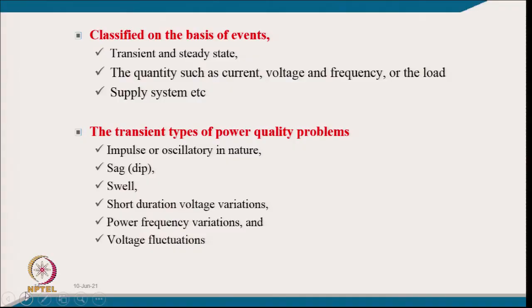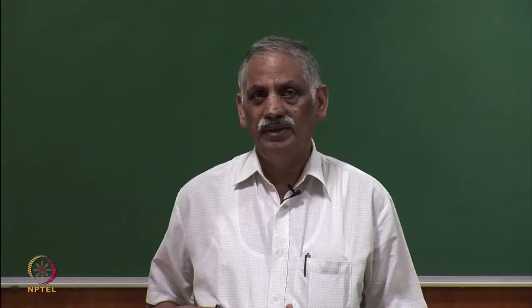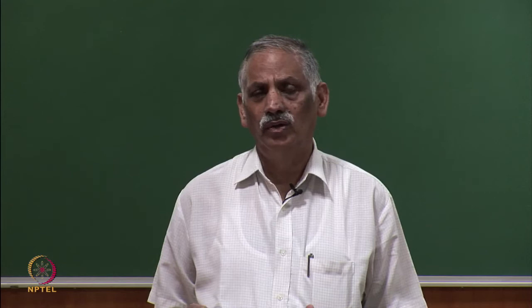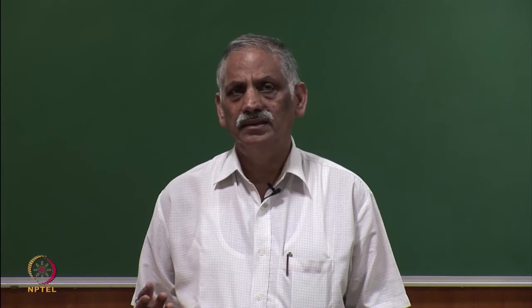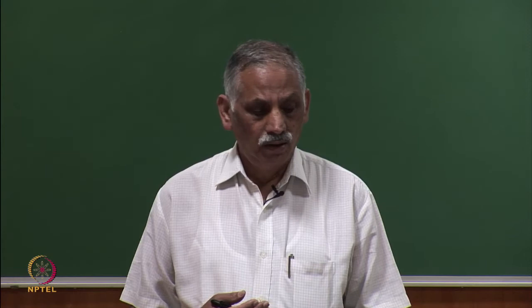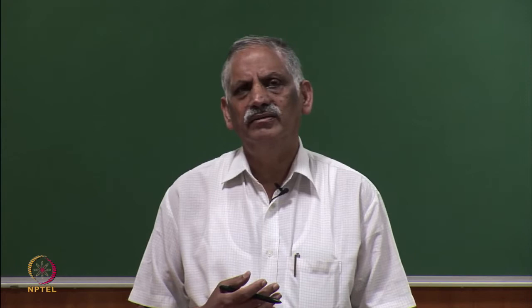Transient power quality problems can be impulsive or oscillatory in nature. Short-duration voltage variations include voltage dip or swell lasting from 3 cycles to maybe a minute. Steady-state problems include long-duration voltage variation — for example, depressed voltage in the evening when overload occurs, making fans run slower and lighting systems not function properly. Voltage waveform distortion also occurs, such as noise in fans when an inverter feeds the home load, causing torque pulses.